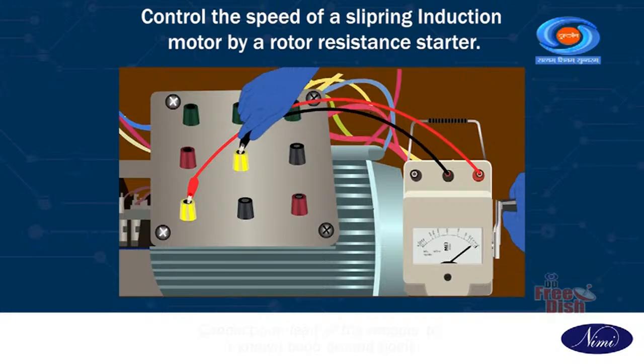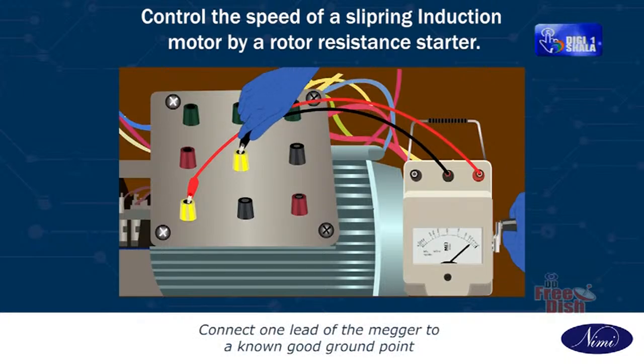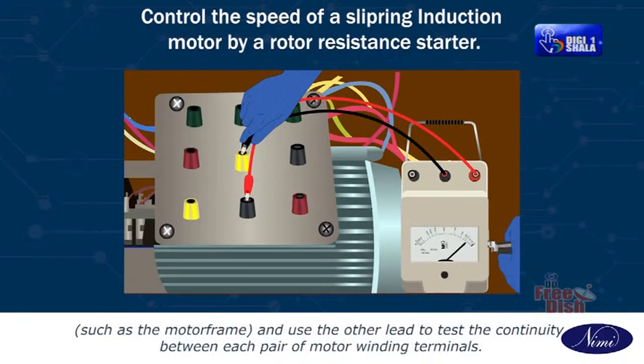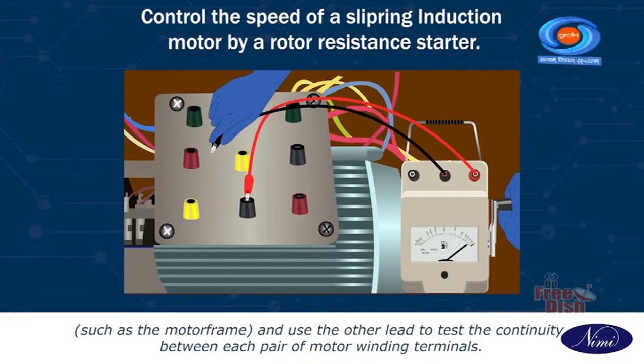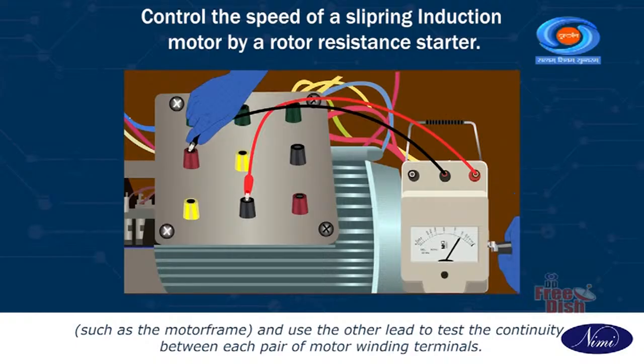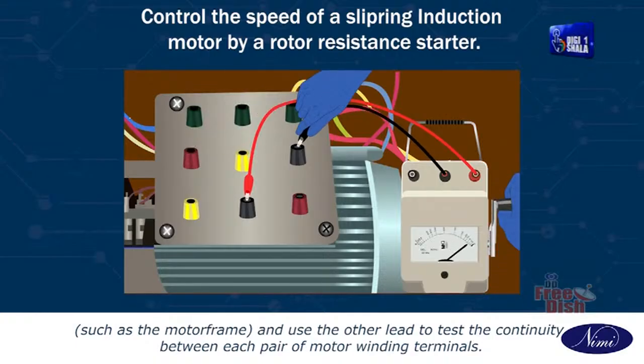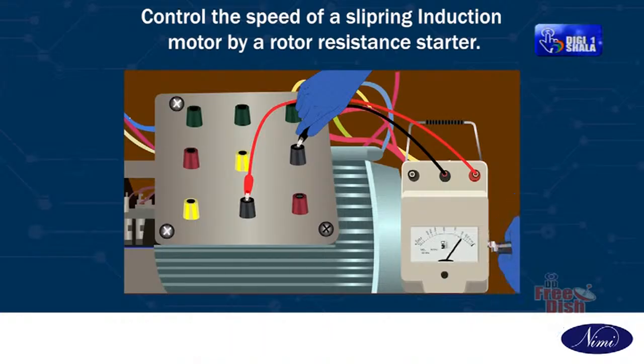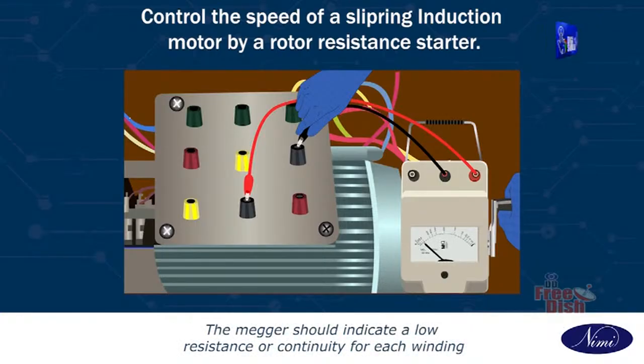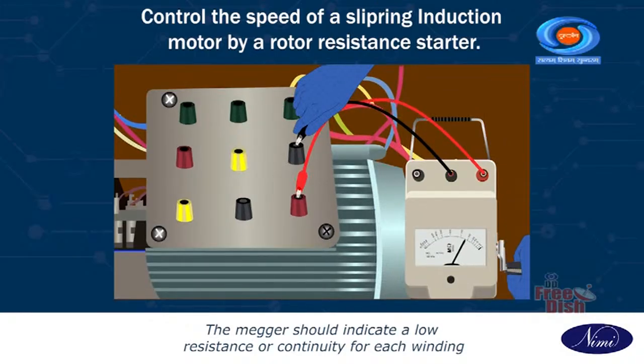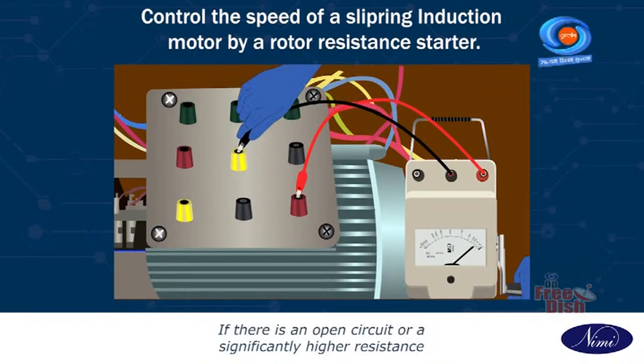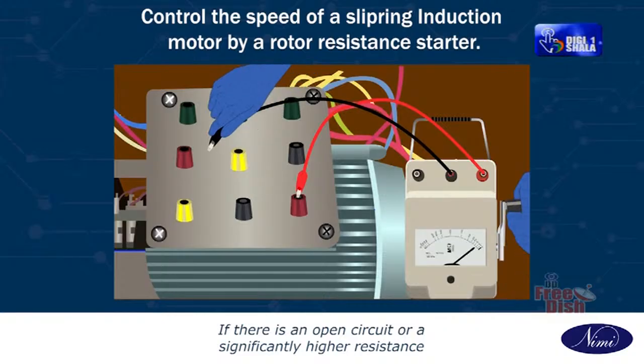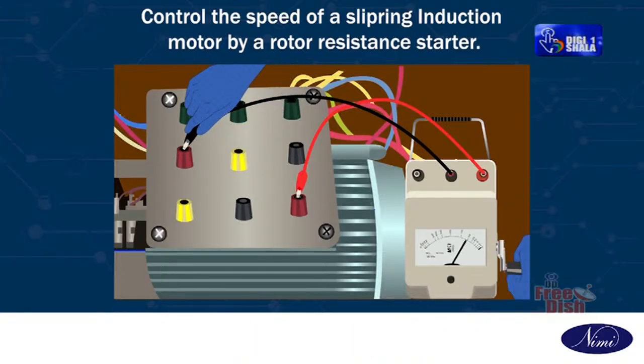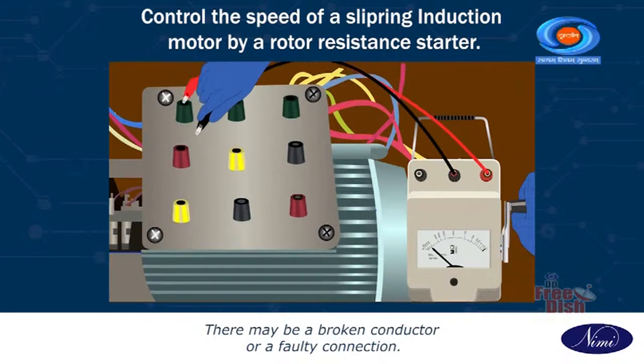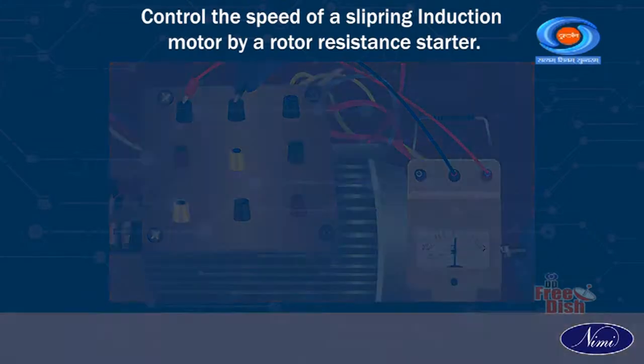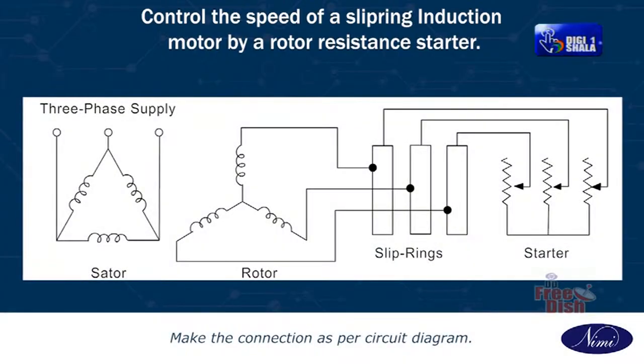Continuity test. Connect one lead of the megger to a known good ground point, such as the motor frame, and use the other lead to test the continuity between each pair of motor winding terminals. The megger should indicate a low resistance or continuity for each winding. If there is an open circuit or a significantly higher resistance, there may be a broken conductor or a faulty connection. Make the connection as per circuit diagram.